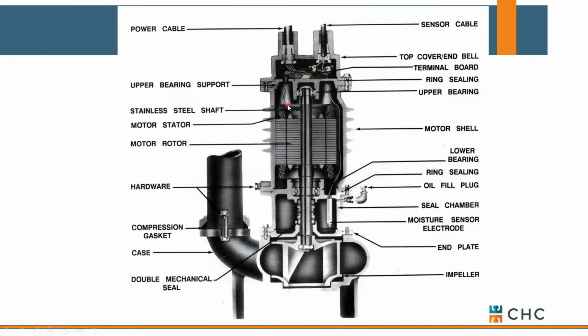There's also a temperature probe inside the windings. It's looking for elevated temperatures. So if we have some debris wrapped around our impeller, or somebody stuck a 2x4 or a mop head down into our basin, and we're drawing excessive amps, that's also going to get transmitted up to our control panel.